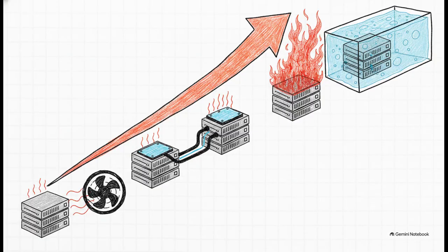As an IT manager, you don't just guess which technology to use, right? You engineer it based on your thermal math. If your entire server rack generates up to 25 kilowatts of heat, you can still probably get away with heavily optimized air cooling. But once you cross that threshold into the 25 to 45 kilowatt range, which is exactly where modern AI systems live, direct-to-chip cooling becomes the ideal, highly efficient choice. And when you start pushing past 40 or 45 kilowatts per rack, or if you're deploying heavy compute in a really tight edge computing location, immersion cooling becomes the necessary standard. You simply match the liquid architecture directly to the heat load.